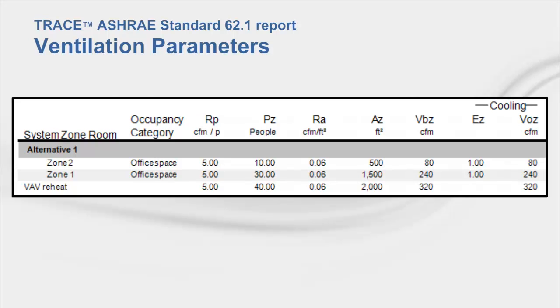In the TRACE 62.1 report, the Zone Ventilation Parameters section will display the calculated V sub BZ and V sub OZ values for each zone in the Cooling and Heating mode. In this report, you can see that TRACE calculated V sub OZ for Zone 1 to be 240 CFM and Zone 2 to be 80 CFM, which aligns with our hand calculations.